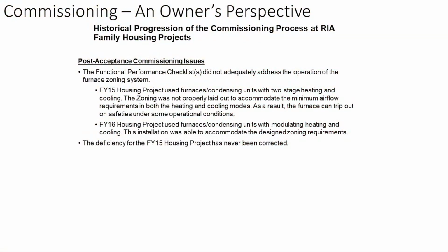The FY15 contractors, though, were a little bit different. They were able to accept what I told them, and they were actually able to set the system up and get it operating. But there were still some design issues. Post-acceptance, we found that because the checklist didn't really check the operation of the furnaces, it just checked to see that the zone dampers themselves opened and closed. It didn't check the system response under heating or cooling.